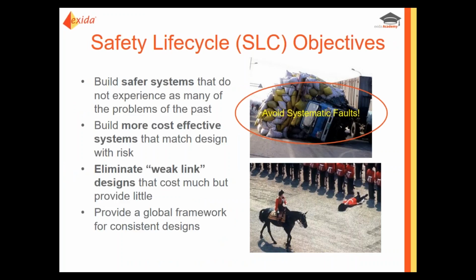problems regarding systematic faults. Systematic faults, some people say, are due to the human factor, but basically it's what we call the 3 Ps: the paperwork, processes, and the people. So if your people aren't trained, if your processes aren't good and your procedures aren't good, you're going to end up with poorly implemented designs, missing requirements, and worse still, you may end up with a lower SIL rating than you actually need.